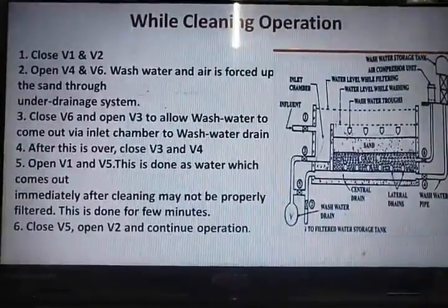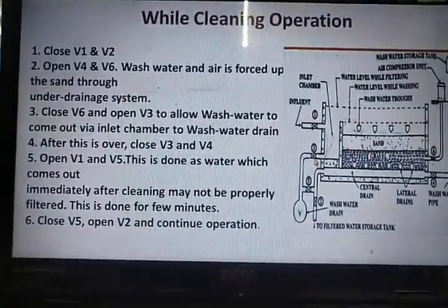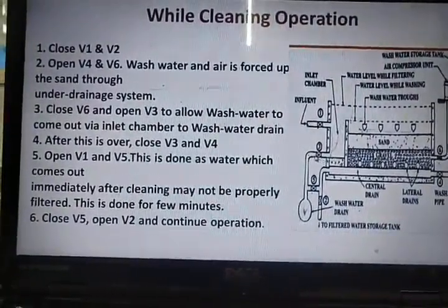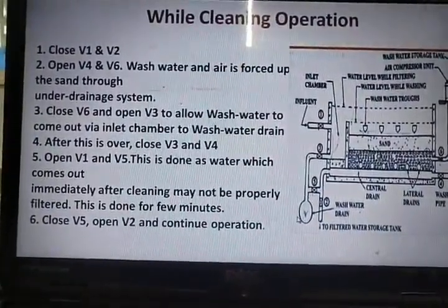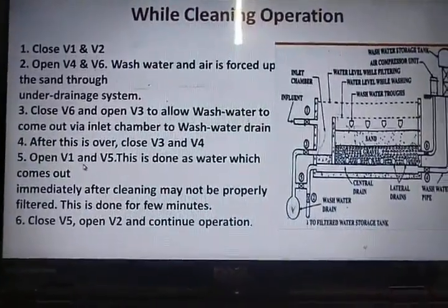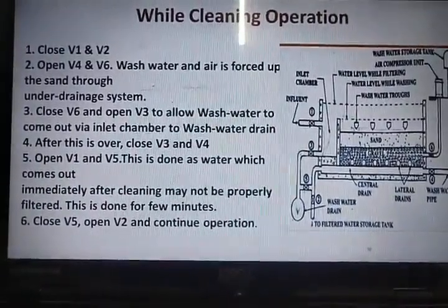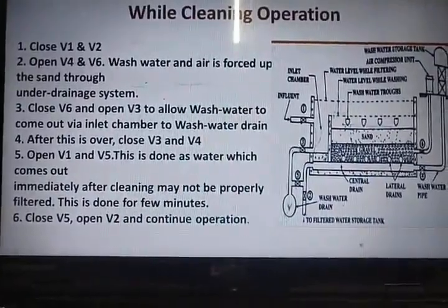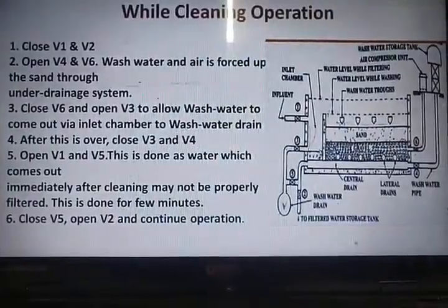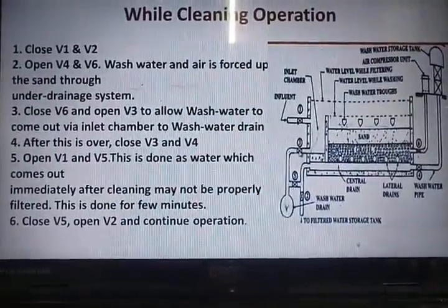Okay, if you open the valve V3 here. Okay, so here you can see the valve V3, the water after backwashing will be collected into this washed water drain through this valve V3. Okay, after this is over, we will close the valve V3 and V4. Okay, that means if you close the V4 valve, then there won't be entry of the backwash water. Okay, and after draining all the water, we'll also close the valve V3.